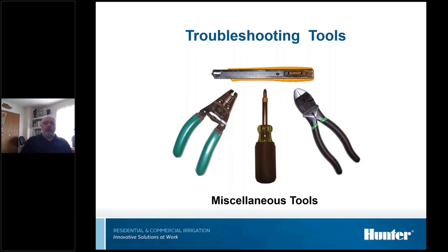That box cutter was used, guys use it when they're installing to get the outer jacket off of our wire. You use the box cutter, and it's actually what 3M recommends you use. What we found was that all you've got to do is score the wire and flex it and it'll pull right off. If you use a box cutter, the tendency is to go right through the outer jacket into the wire insulation and put a nick in it. And you won't even know you did it. But a couple of years from now, you will, when you go back out and have to fix that wire where it corroded out where that nick is. So I advise everybody, don't use box cutters or knives. Just use your wire tool. All you've got to do is put a little bit of score on the outside of that wire and it'll break off for you.